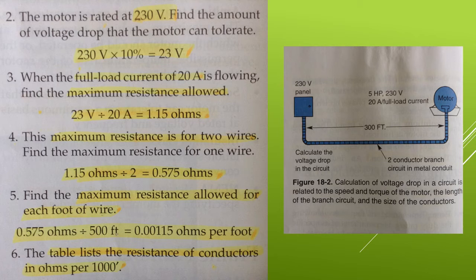Step 4, this is the maximum resistance for 2 wires. So to find the maximum resistance for 1 wire, we just divide the value in ohms by 2, in this case 1.15 ohms divided by 2 equals 0.575. Again, 0.575 ohms.